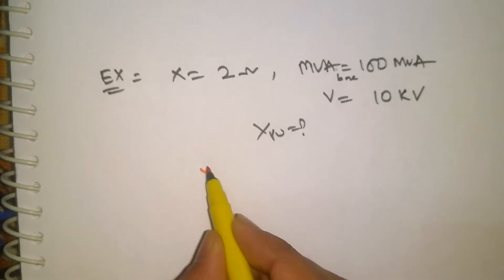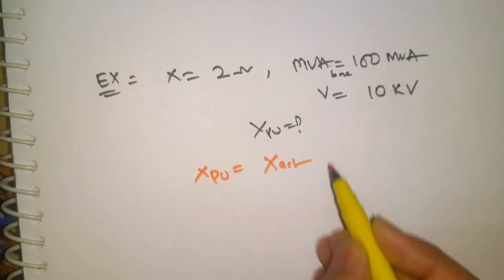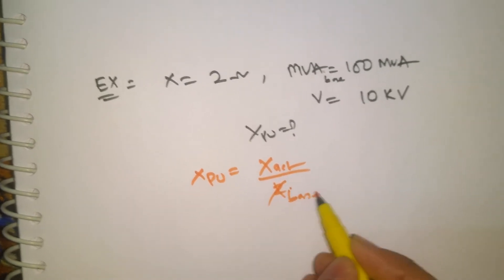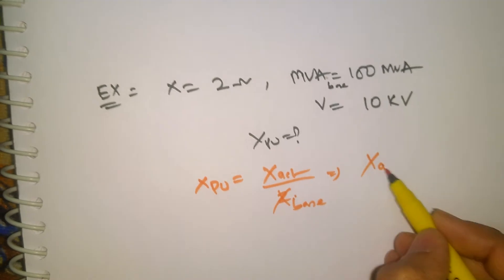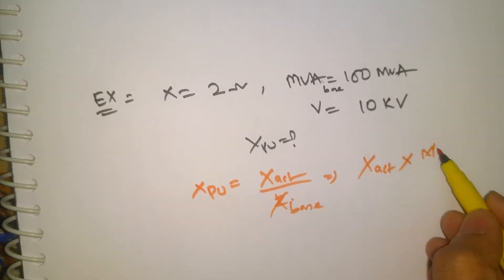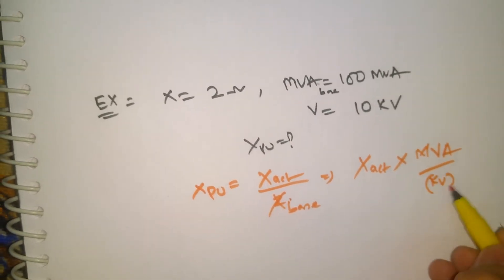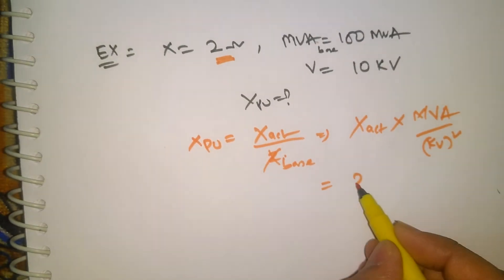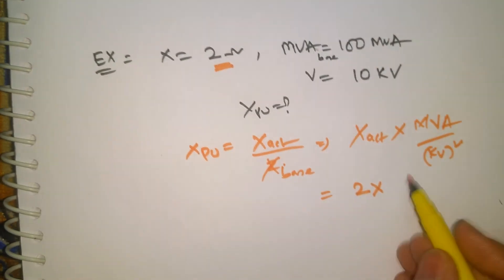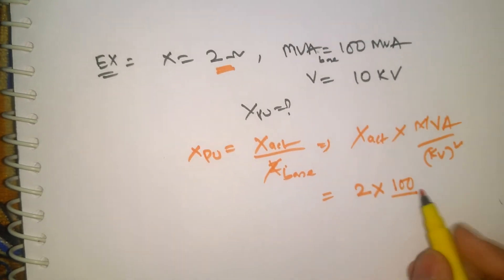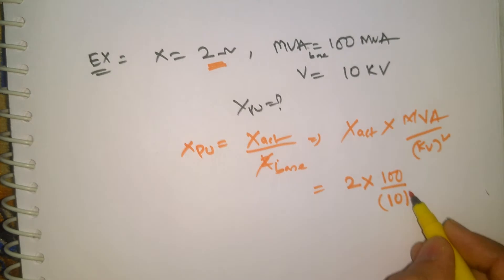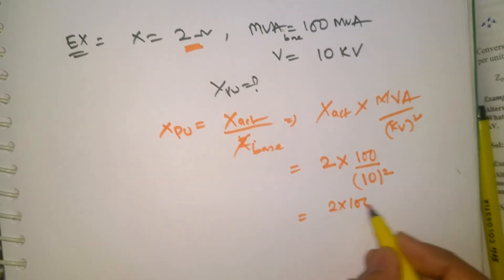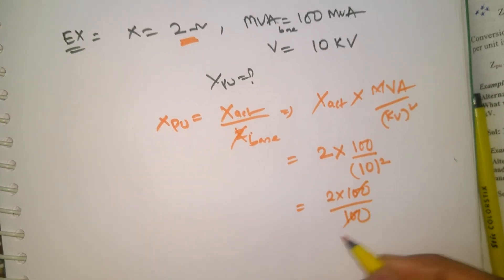As explained, X per unit equals X actual divided by X base, and X base equals KV squared divided by MVA. So X per unit equals X actual times MVA divided by KV squared. For example, X actual is 2 ohms, MVA is 100, KV is 10. So: 2 times 100 divided by 10 squared equals 2 times 100 divided by 100.